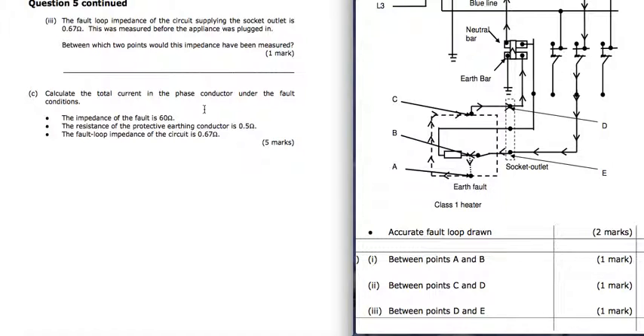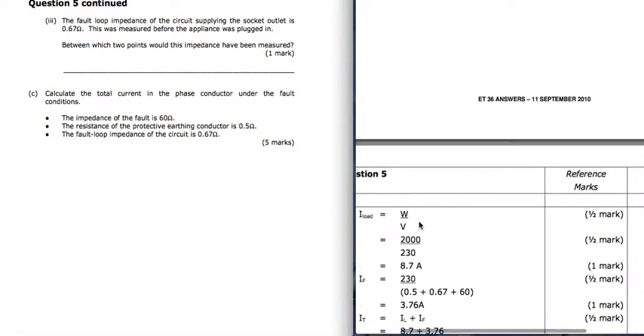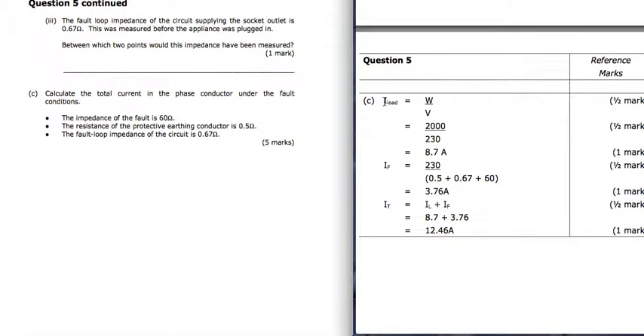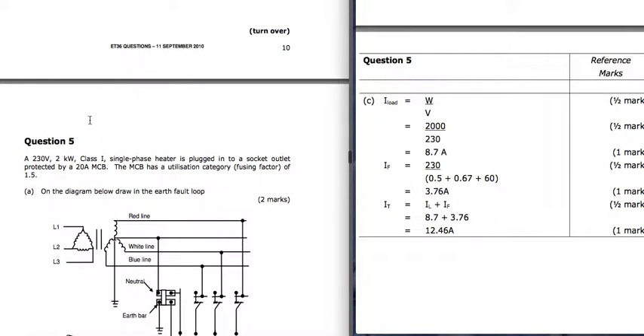Calculate the total current in the phase conductor under the fault conditions. Now this is another one where you need to find the fault current, and then you need to add the normal current. So let's have a look how they've done it here. The normal current, the current in the load, would be the power divided by the voltage. So you're given the power here, it's a 2 kilowatt heater. So 2 kilowatts, 2000 watts, divided by 230 gives me 8.7 amps. That's the normal current flowing in the circuit.